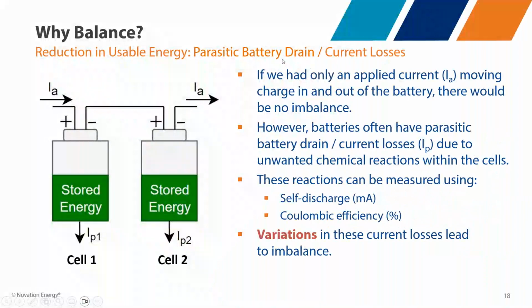So why balance? Here's a very simple model of two different battery cells. You have your stack current, which is the same current going through both cells in the same stack, and if it was only that, the system would stay balanced. However, cells have a parasitic battery drain of current losses, modeled here as IP1 and IP2, and it's possible for these parasitic currents to be slightly different between cells, due to manufacturing tolerances and chemical differences.